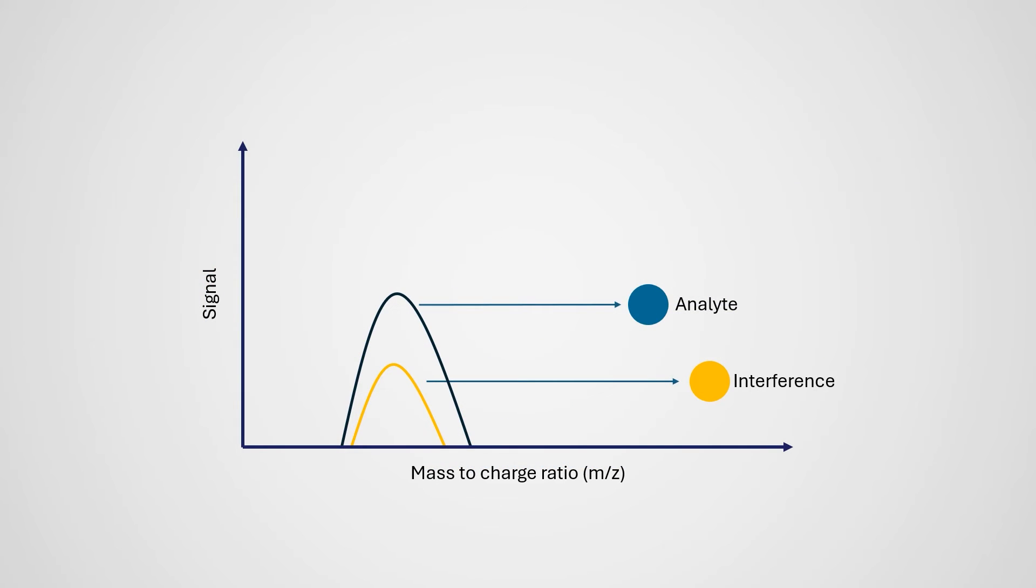This portion of the instrument can also be run as a reaction cell, which uses chemical reaction with hydrogen gas to add a proton to an analyte ion. This shifts its mass to charge ratio by one. That is often enough to separate your desired signal away from an interfering one.